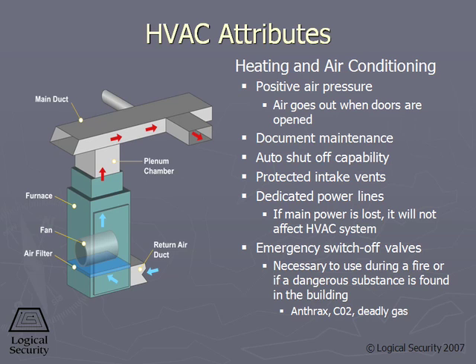We should always document the maintenance of the heating, ventilation, and air conditioning systems. We should know how to shut these down. Our security personnel should first be made aware that it's their responsibility to turn off the HVAC system in case of fire, and they should then be trained on where and how to do this properly. We should protect the intake vents, because this would be an area where a bad guy could put some sort of toxic fumes or gas or something even more volatile into the air conditioning system, and this could proliferate through the entire facility. They should have dedicated power lines.